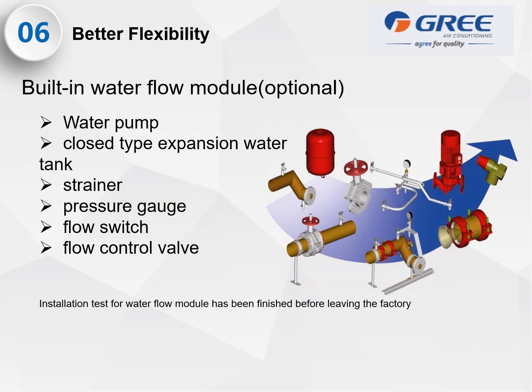You can request this type of configuration if you want a built-in water flow module, water pump, a closed type expansion water tank, strainer, pressure gauge, flow switch, or flow control valve. Installation test for water flow module has been finished or will be completed before leaving the factory.